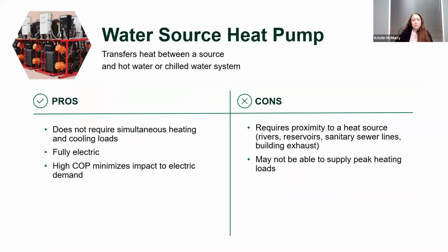Similar to the heat recovery chiller, it might not be able to supply your peak heating loads. So it's pretty case by case, but it is an electric option. It doesn't require simultaneous heating and cooling loads, and it's got a potentially good COP - a typical one we'd see is maybe around 4.5. Pretty good.